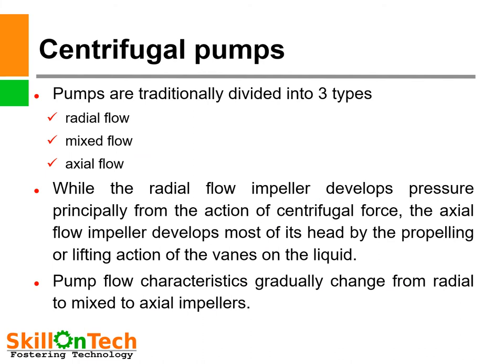Pumps are traditionally divided into three types: radial flow, mixed flow, and axial flow. While radial flow impellers develop pressure principally from centrifugal force, axial flow impellers develop most of their head by the propelling or lifting action of the vanes on the liquid. Pump flow characteristics gradually change from radial to mixed to axial flow impellers.